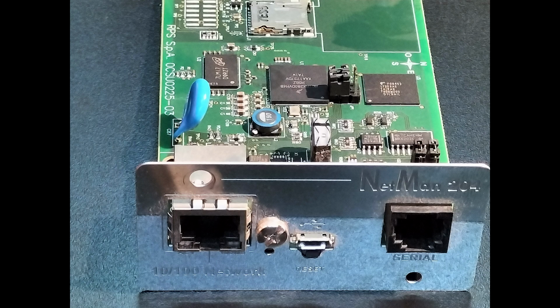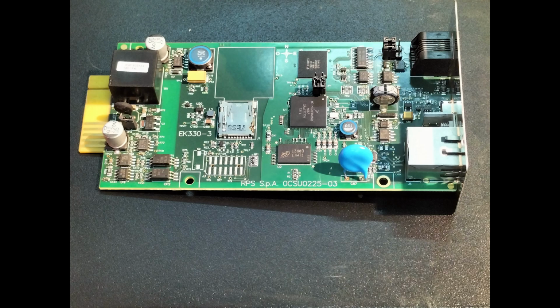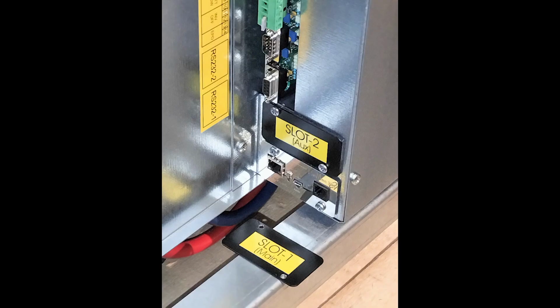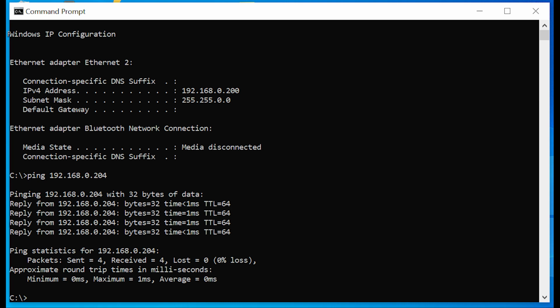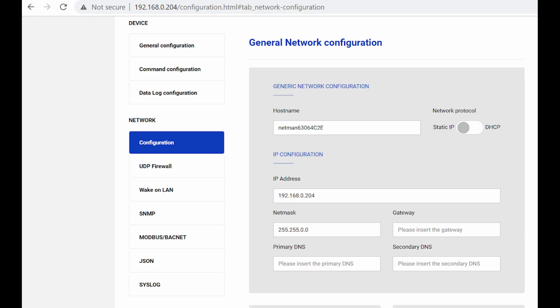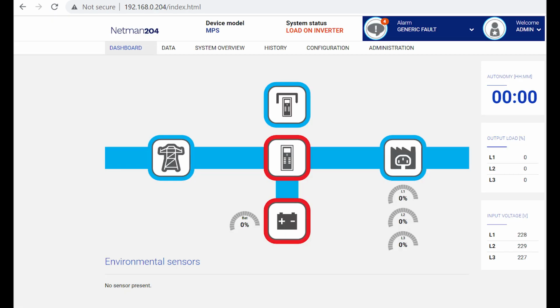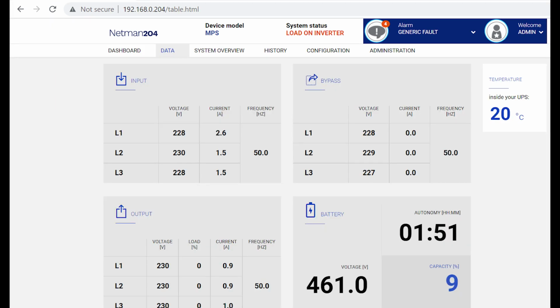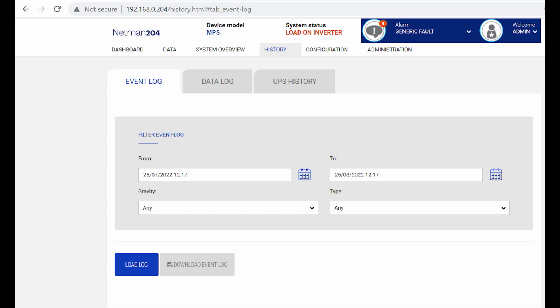For applications that require remote UPS health checks and diagnostics, the Netman 204 will stream important UPS operational data via a network to a web browser anywhere in the world. For this demonstration, the Netman 204 is configured with a static IP address and using Google Chrome to view its web pages. The dashboard indicates all essential operating parameters and data. At a glance, input, output, and load conditions can be assessed, as well as any alert the UPS may have generated. Battery test and authorized static bypasses can also be remotely activated.